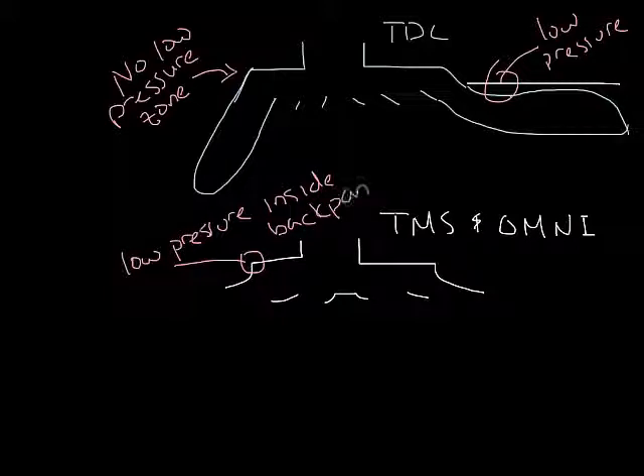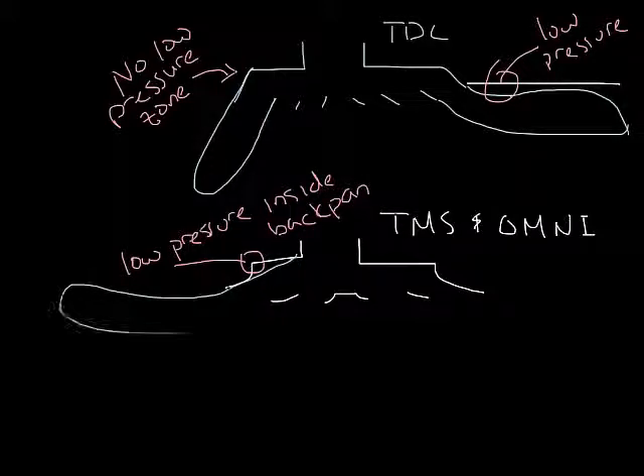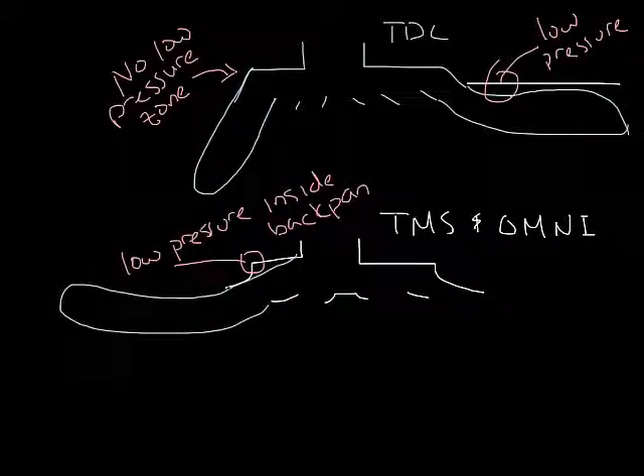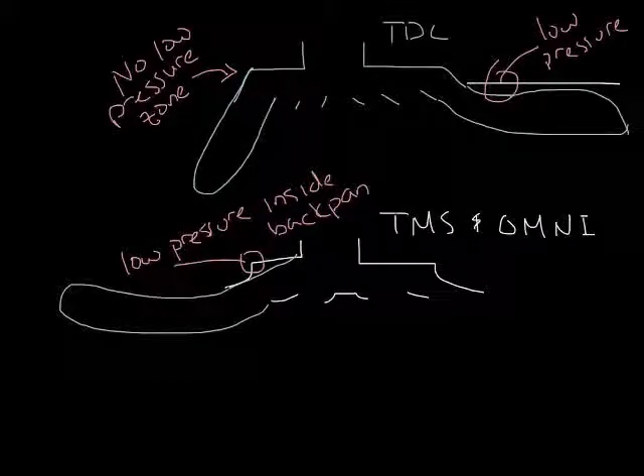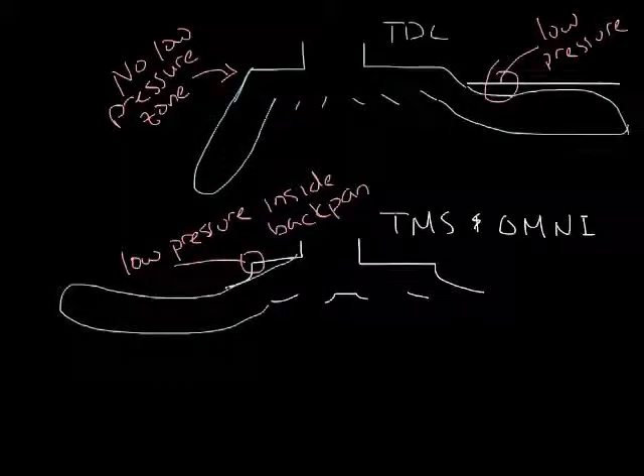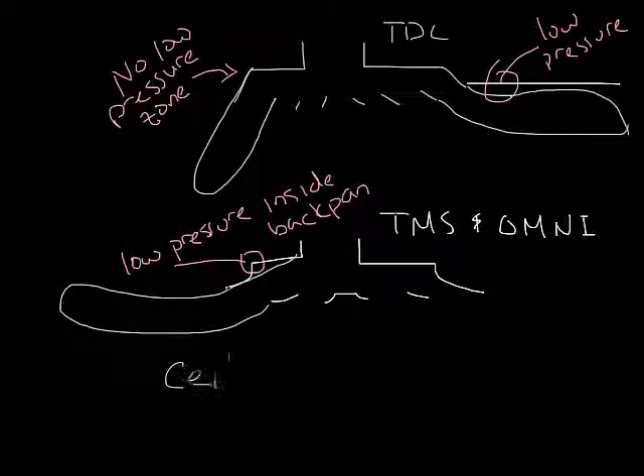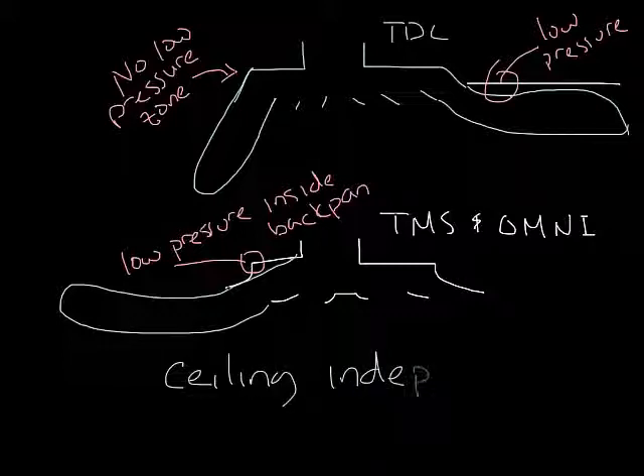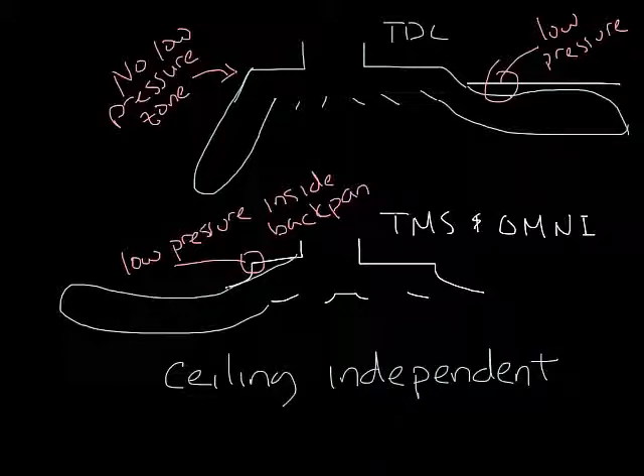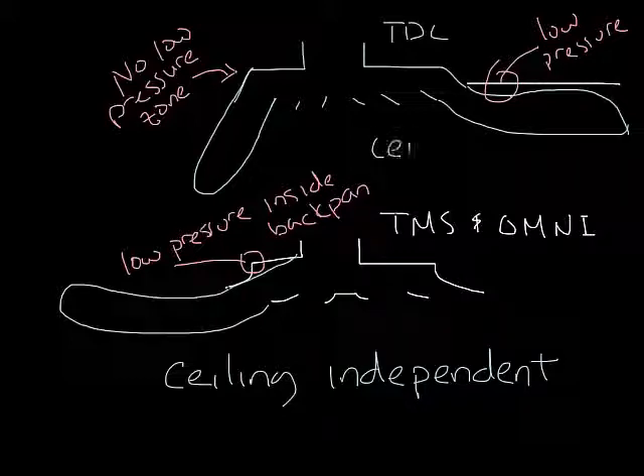So as the air leaves this diffuser, this low pressure zone pulls the air up and maintains a ceiling-like pattern without the ceiling. This is called a ceiling-independent diffuser. And then the TDC, or this type of diffuser up here, is ceiling-dependent.